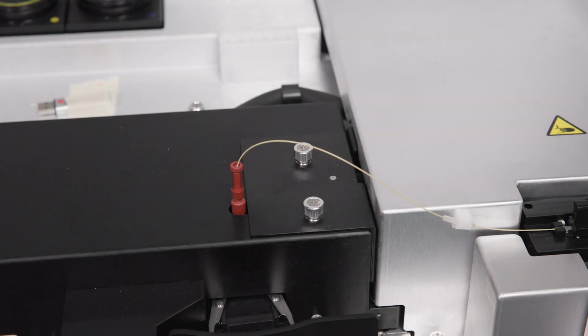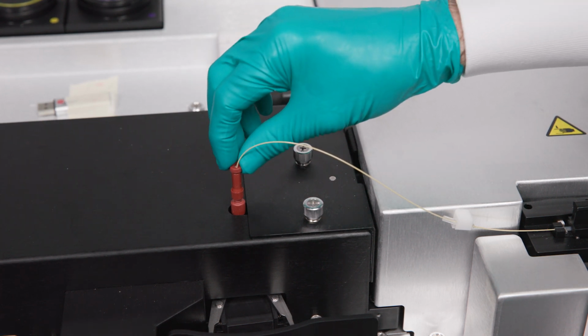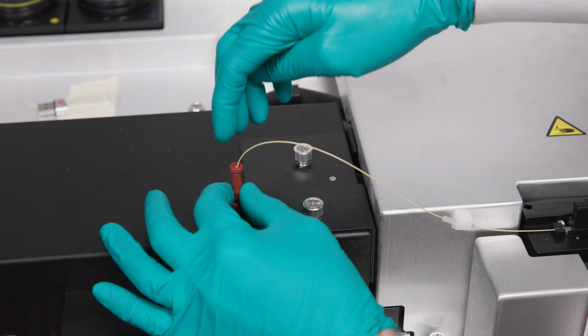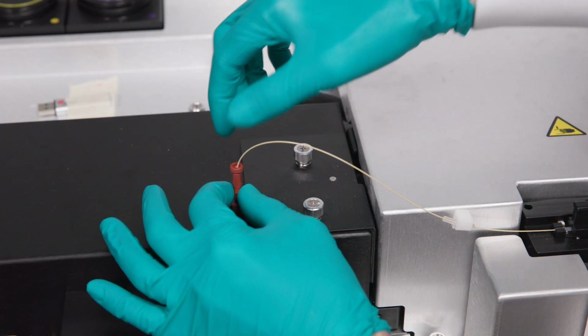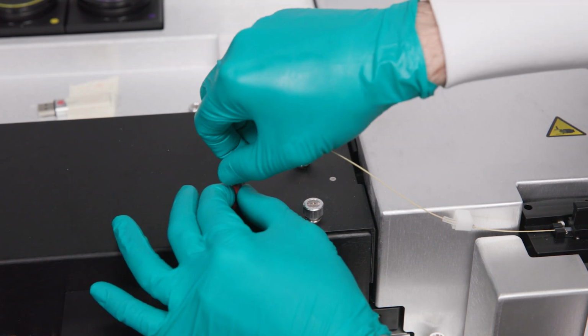If you experience sample line clogging, you may need to remove and clean or just fully replace your sample probe and sample line. You need to start with removing the clogged line. Start here with these red connections. These are just finger tight. You're only going to remove this top one.